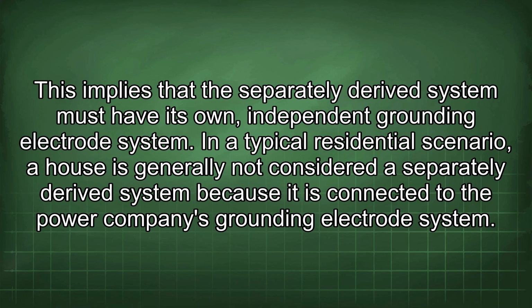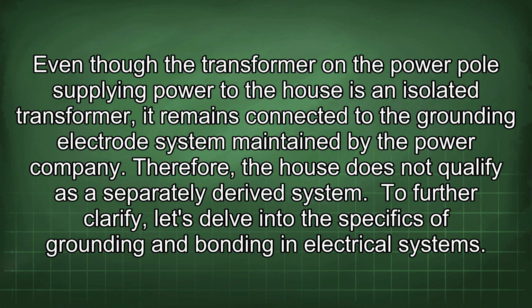In a typical residential scenario, a house is generally not considered a separately derived system because it is connected to the power company's grounding electrode system. Even though the transformer on the power pole supplying power to the house is an isolated transformer, it remains connected to the grounding electrode system maintained by the power company. Therefore, the house does not qualify as a separately derived system. To further clarify, let's delve into the specifics of grounding and bonding in electrical systems.